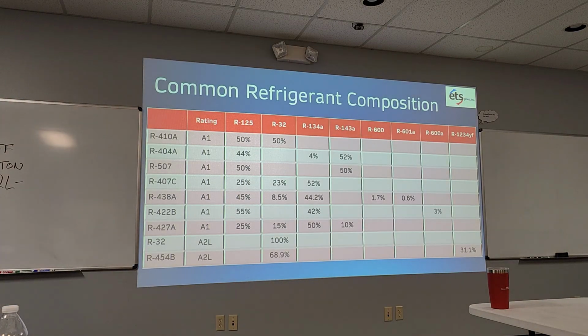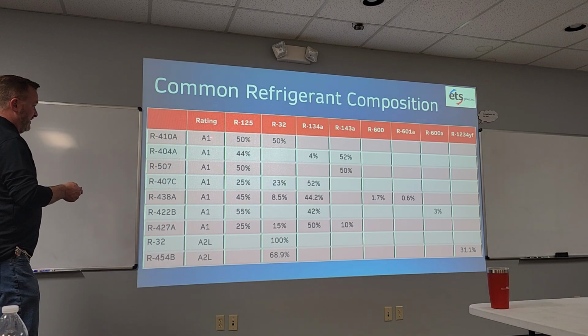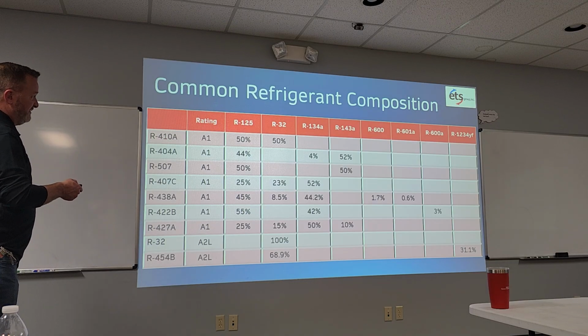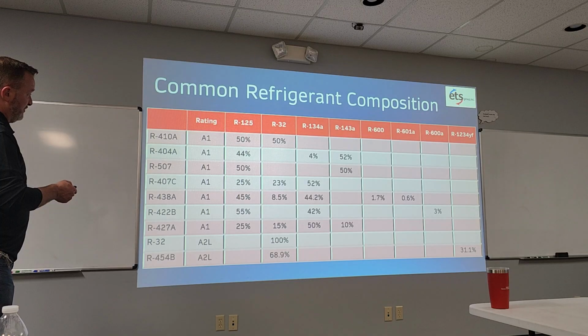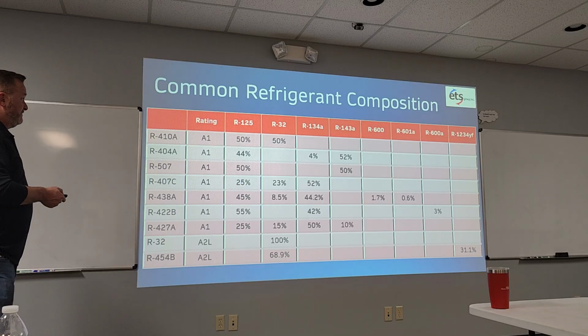Here's a lot of your common refrigerant compositions. Some of the big ones, like I was talking about before, you got 410A here, it's an A1 refrigerant, 50 and 50. So you've got 125 in there, as I was talking about, that's that problem refrigerant. Look at how many refrigerants it's in, right? It composes a lot of these refrigerants. So the interesting thing is, 410A is also 50% R32.